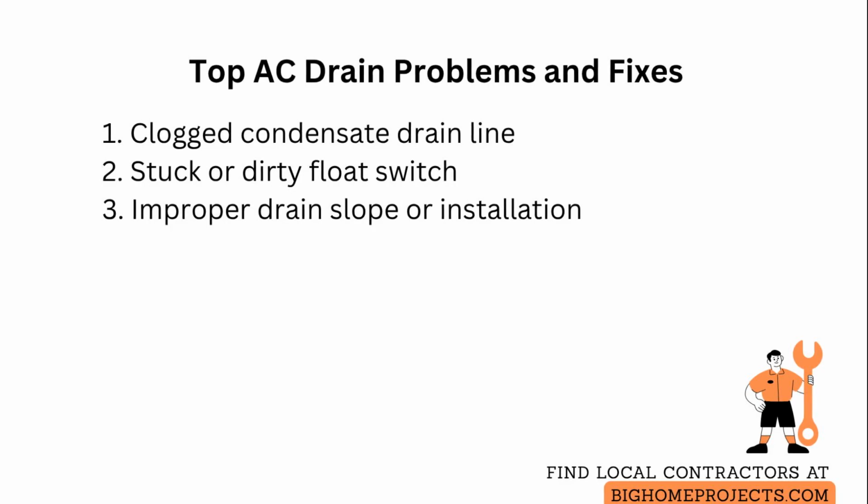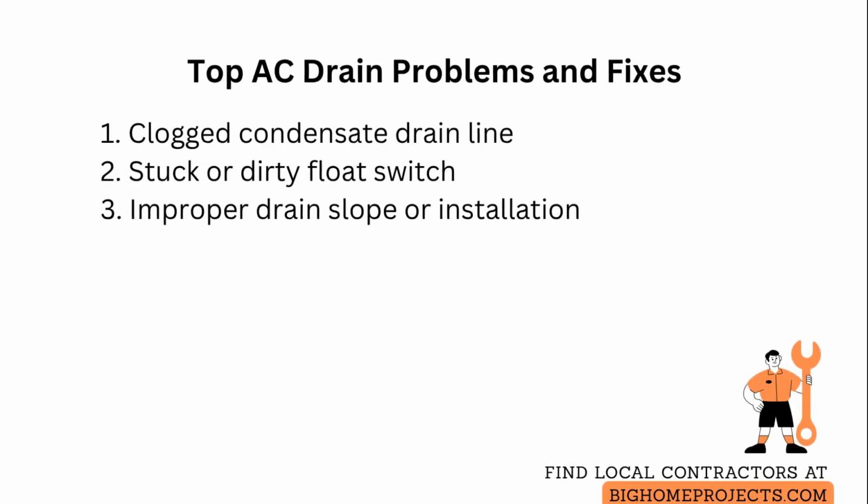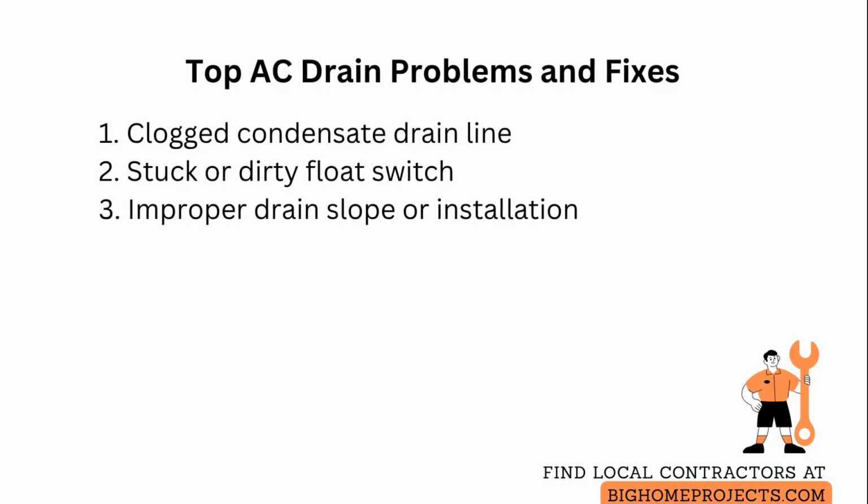Another frequent problem is a stuck or dirty float switch that fails to reset or trips prematurely. Clean the float and housing, verify freedom of movement, and if it still sticks, replace the switch.